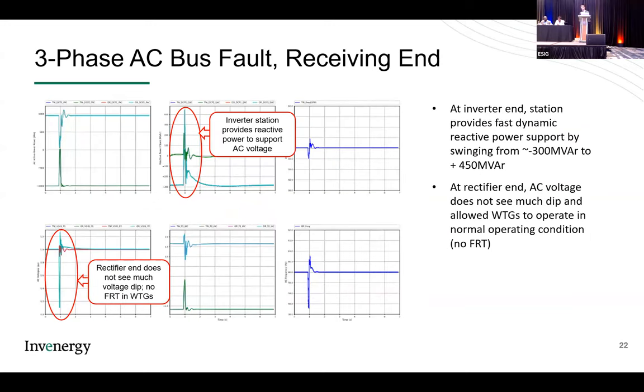And so this is kind of where we get into some of the system benefits that Hannes and Chandra were talking about, that these converter stations can independently control reactive power. And you can see the inverter station provides VARs to try to support the AC voltage at that bus that was faulted. Meanwhile, the rectifier end can keep that grid forming islanded system. There's not much voltage dip. The turbines don't go into fault ride through because they don't see much. They see the AC chopper as the load instead of the remote end.